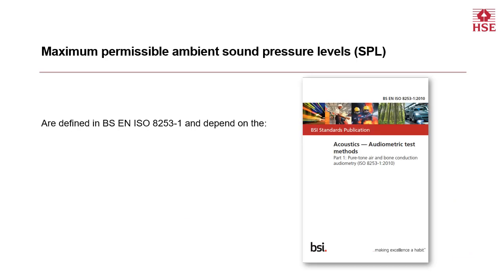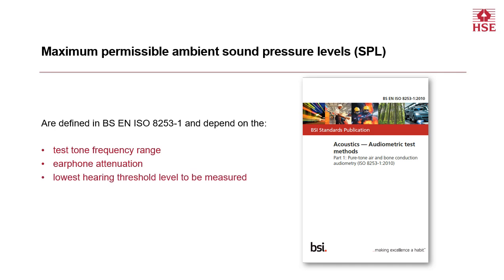The maximum permissible ambient sound pressure levels for air conduction pure tone audiometry are defined in BS EN ISO 8253-1, and they depend on the test tone frequency range, the earphone attenuation, and the lowest hearing threshold level to be measured. So let's consider each of these in turn, starting with the test tone frequency range.